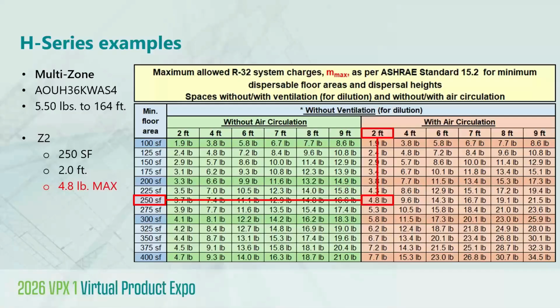So the challenge is we've got a system charge of 5.5 pounds that you see on the upper left. So we're looking at the 36KWAS4. Factory charge is 5.5 pounds up to 164 feet of total line length. We can only manage 4.8, but we need 5.5.